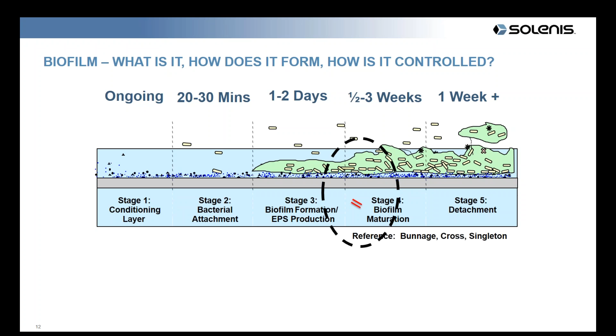So how do we treat that? Traditionally we've used oxidizing biocides, and they work pretty well on the planktonic bacteria, but not so well on eliminating the biofilm itself. An oxidizing biocide is like a blowtorch, trying to burn everything it comes in contact with. It doesn't necessarily penetrate that extracellular polysaccharide layer, or it gets burned up trying to penetrate it.